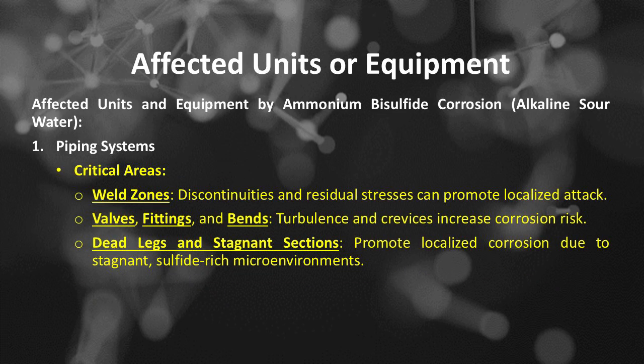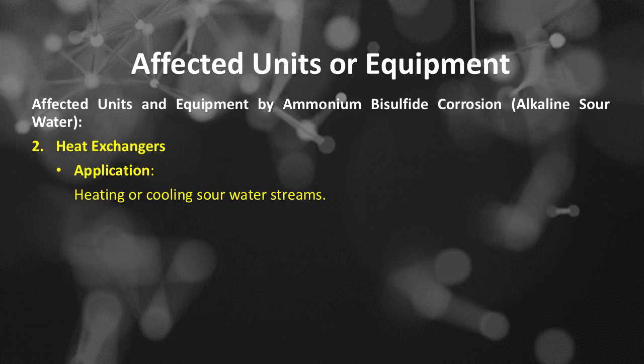The critical areas of piping systems include weld zones, where discontinuities and residual stresses can promote localized attack; valves, fittings, and bends, where turbulence and crevices increase corrosion risk; and dead legs and stagnant sections, which promote localized corrosion due to stagnant, sulfide-rich microenvironments.